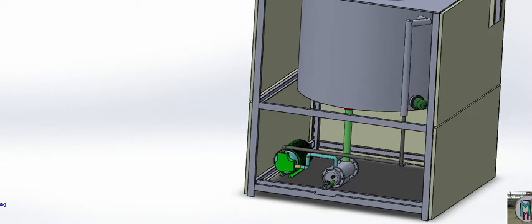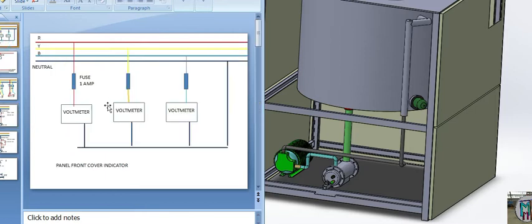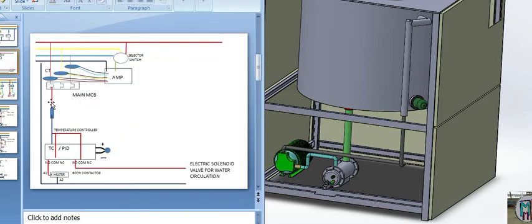Now you can see the voltmeter for every phase; in each phase you have to put a voltmeter. And this CT we already described in our previous video. This is the temperature controller or PID. We suggest to everybody that a PID must be there, because it is our experience that if there is a PID, you can get more accuracy from this. The main supply will come through the phases, and after that there are two coils, one coil for heating and one coil for your cooling system.